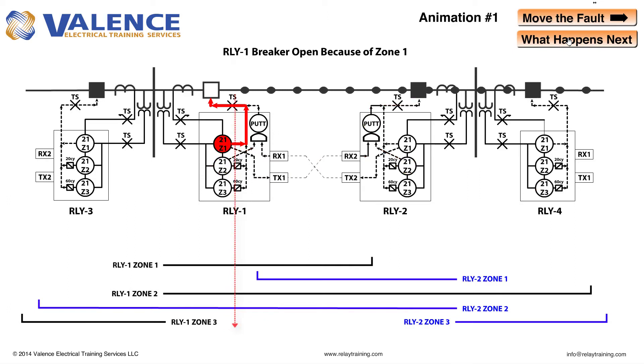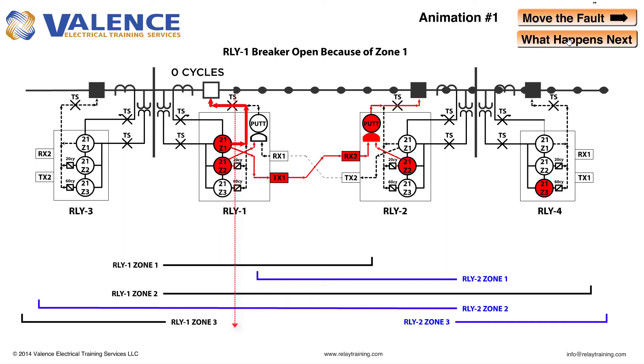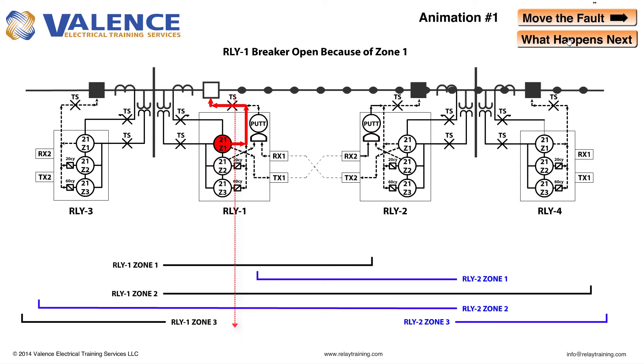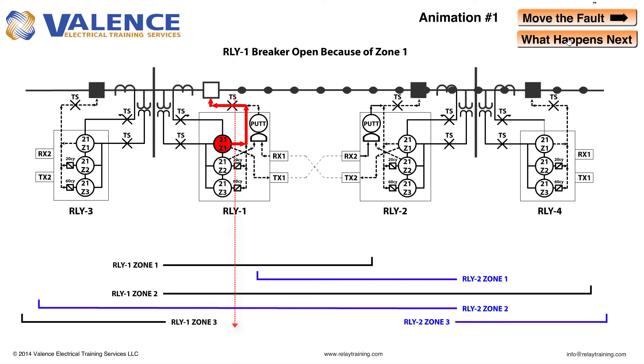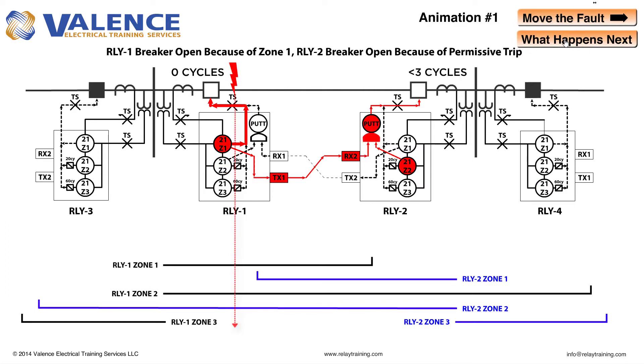How long will it take before Relay 2 trips? Relay 2 would normally trip after a 20 to 40 cycle Zone 2 time delay in a normal impedance protection scheme, but we're using a PUTT scheme here. Relay 2 receives a permissive underreaching transfer trip signal from Relay 1. If Relay 2 receives permission to trip from Relay 1 and it detects a fault on the line via the Zone 2 pickup, it is allowed to trip faster after a small communication time delay. So Relay 2 is going to trip in a significantly shorter amount of time using a PUTT scheme compared to your traditional distance schemes.